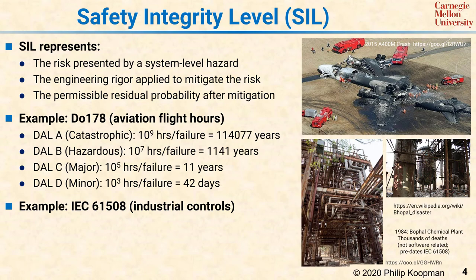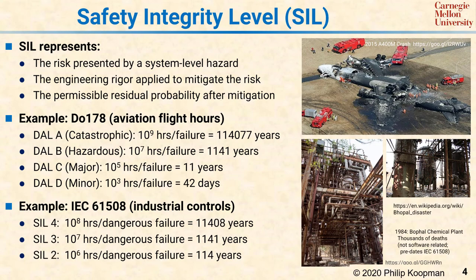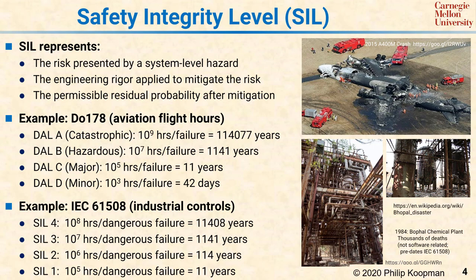IEC 61508 has four SILs defined, with SIL 4 allocated a permissible failure budget of once every 11,000 years. It should be noted that the exposure and operational scenarios for this standard are a bit different than aircraft, which explains the slightly different number. One significant difference is that a chemical processing plant can usually be shut down to be made safe, whereas an aircraft has to keep flying potentially for several hours to a diversion airport after a failure. The SILs in IEC 61508 have a factor of 10 difference in permissible failure rates, with SIL 1 failures only permitted once every 11 years. Other industries have their own safety standards with varying permissible failure rates, but they generally follow the idea that risk determines a permissible failure rate at that particular SIL, and life-critical failures tend to be targeted at tens or hundreds of millions of hours, or even billions of hours, between adverse events.